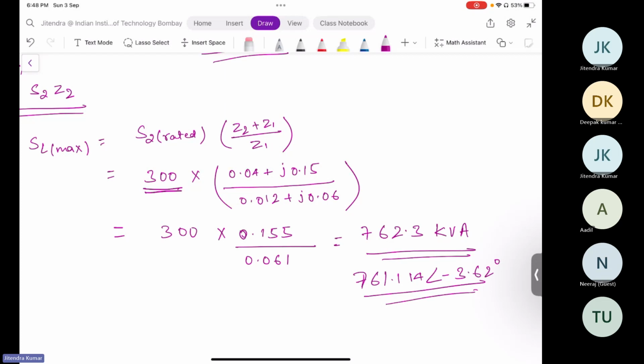Hence transformer 2 should not get overloaded; it is certain that transformer 2 will be overloaded first. So we have to avoid that case. You are perfectly correct, one of the transformers should not get overloaded.